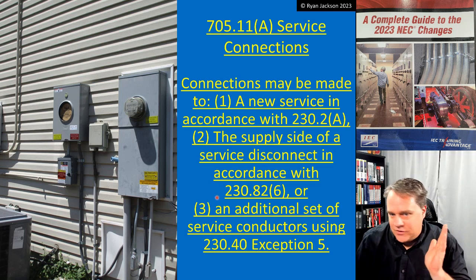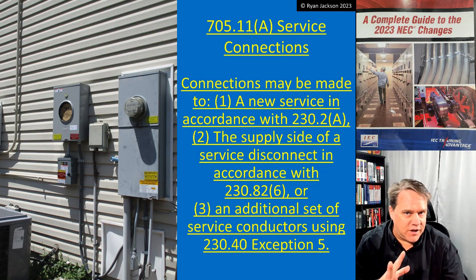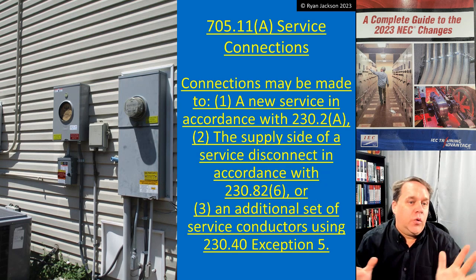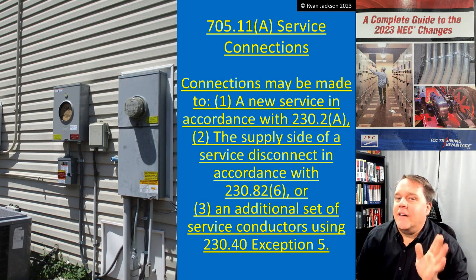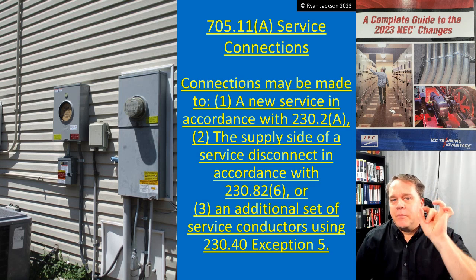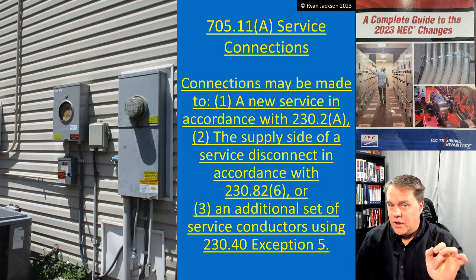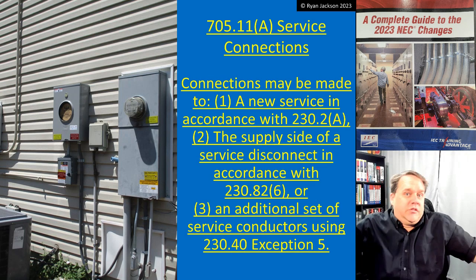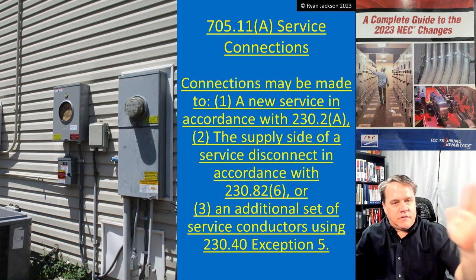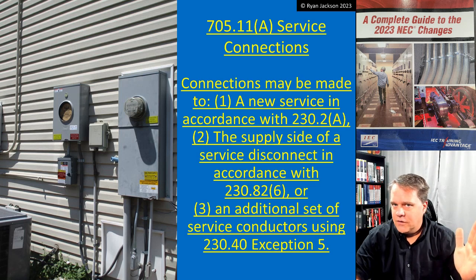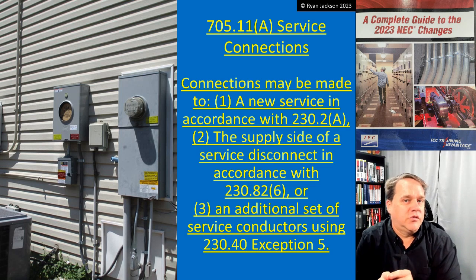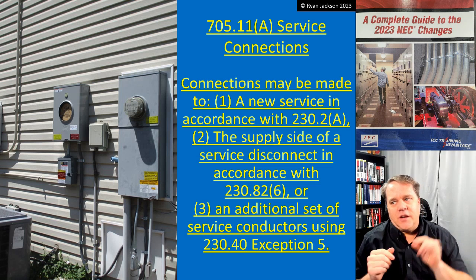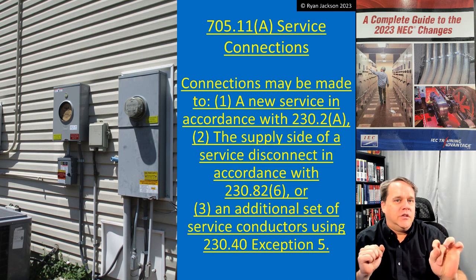How many service disconnects can I have? A lot of people quickly say six, and that's true — you can have six service disconnects per service. But it's not per building. If you have a massive building with two services, you could have six disconnects on one side and six on the other, with signage. If you read 230.72, it's six service disconnects per set of permitted service entrance conductors. The general rule in 230.40 says each service can only supply one set of service entrance conductors — but there are five exceptions to that.